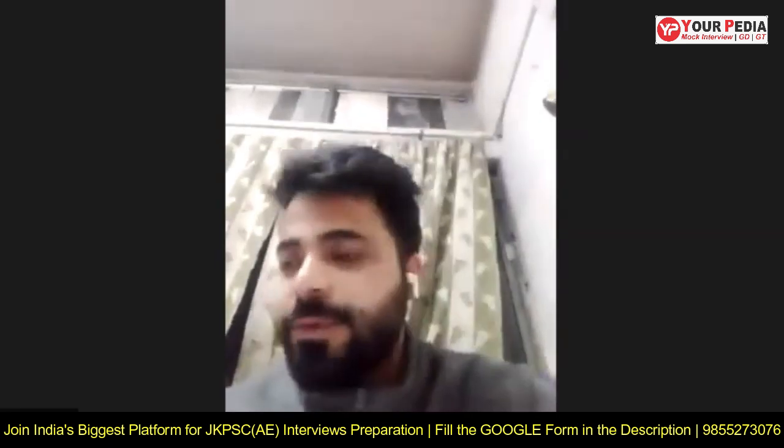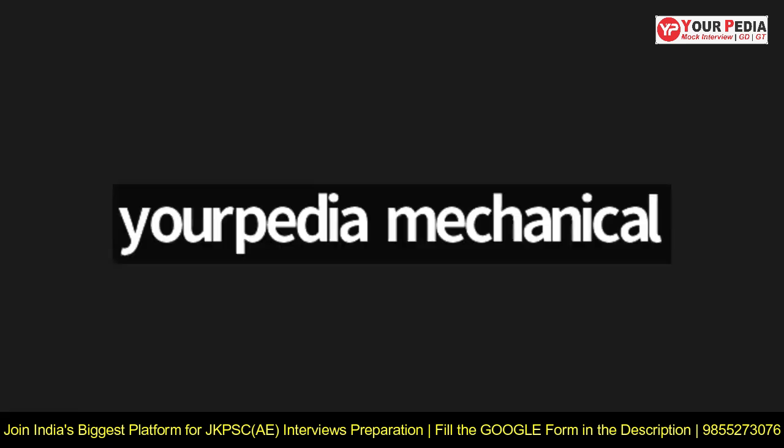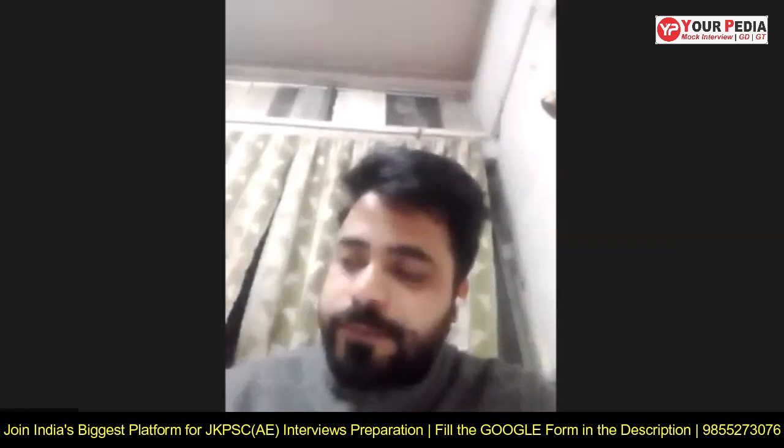Reserve factor. What is the reserve factor? You know, in a power plant, there is a power plant capacity that is known as the rated power. Suppose you are having a particular power plant which is having some capacity, suppose 200 megawatt. So that is the rated power of the plant. That is not the maximum load. Suppose the maximum load on the plant is 150. So how much power are we keeping in reserve? 50 megawatt. Why? For meeting the future demand.